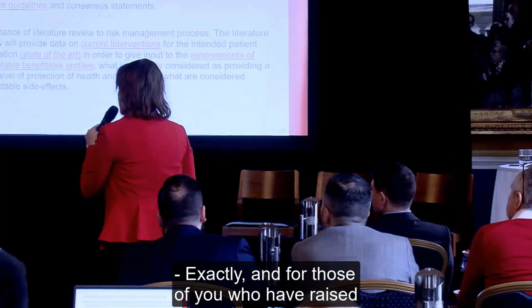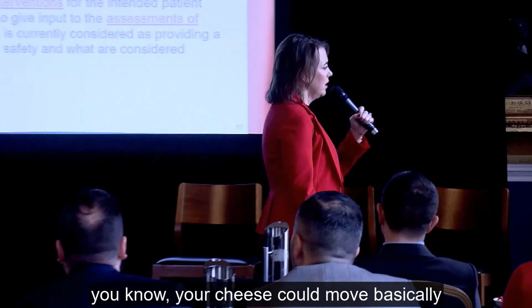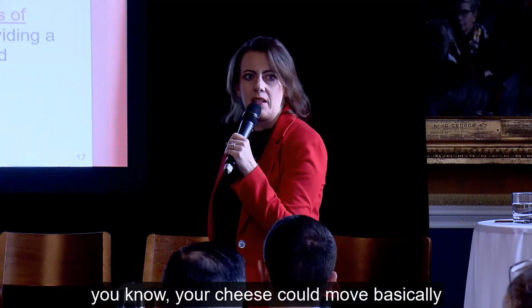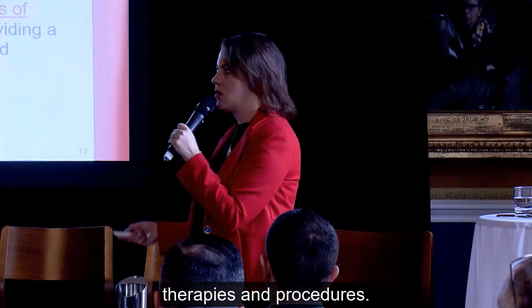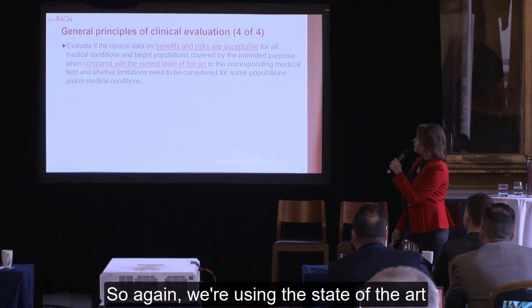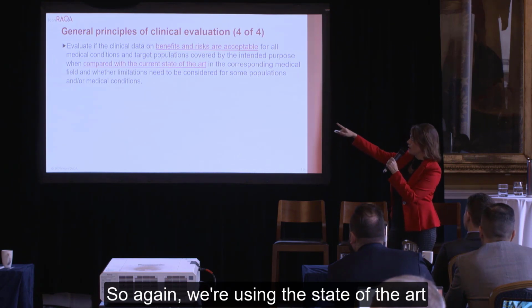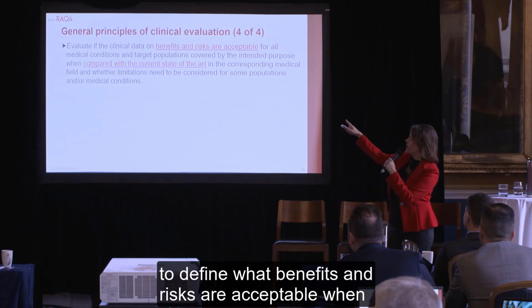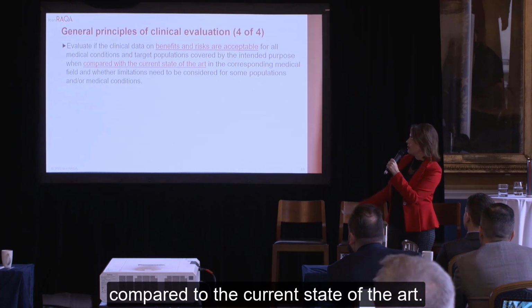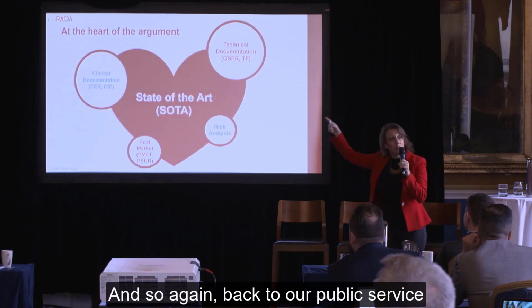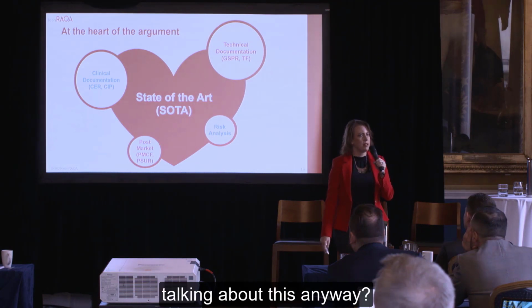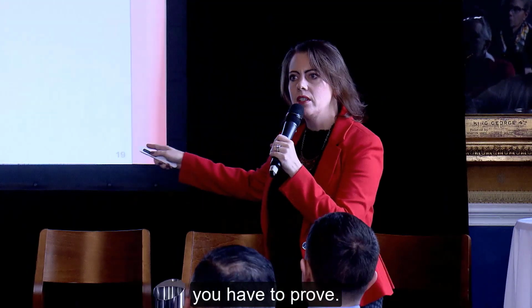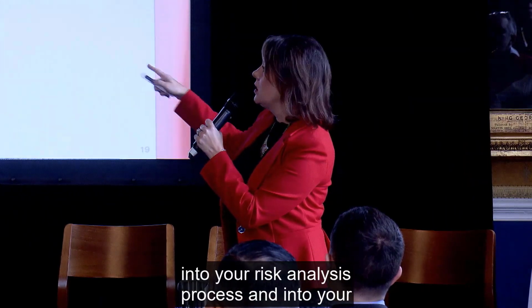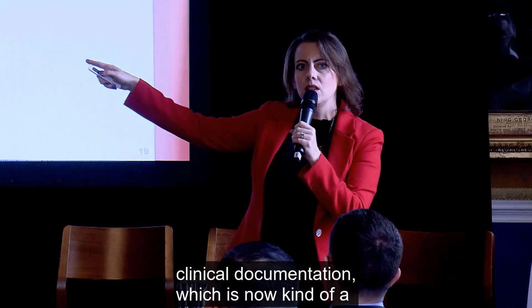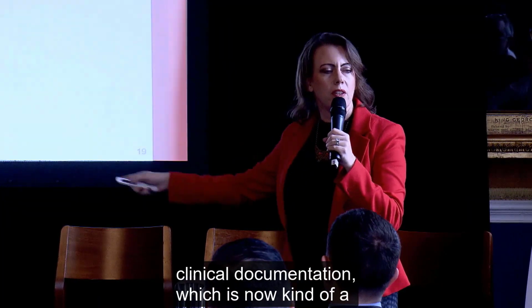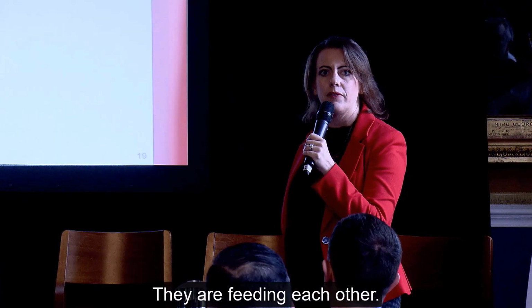Exactly, and for those of you who have raised multi-million dollars or more in funding, your cheese could move, basically, in these alternative therapies and procedures. So, again, we're using the state of the art to define that benefits and risks are acceptable when compared to the current state of the art. And so, again, back to our public service announcement about why we are talking about this anyway. This is at the heart of everything you have to prove. So now we have tied state of the art clearly into your risk analysis process and into your clinical documentation, which is now kind of a circular loop, these two processes feeding each other.